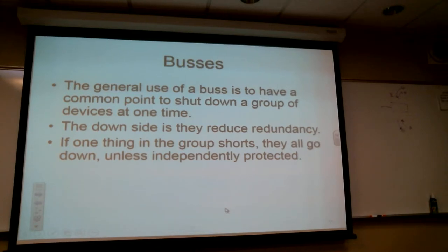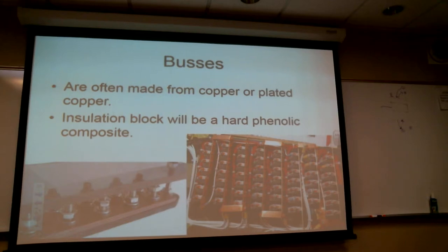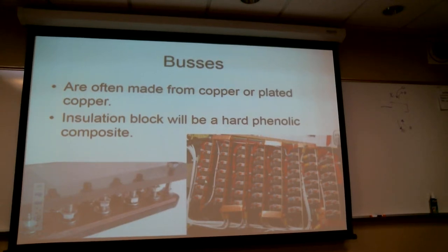The downside is buses do reduce redundancy. If something shorts here and you have to turn that circuit off, look at all the different circuits you're turning off — all of that gets taken offline because of a problem with one. Whereas on a smaller bus, you only lose three things.